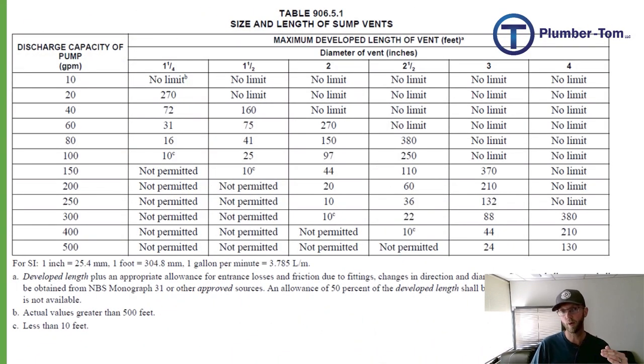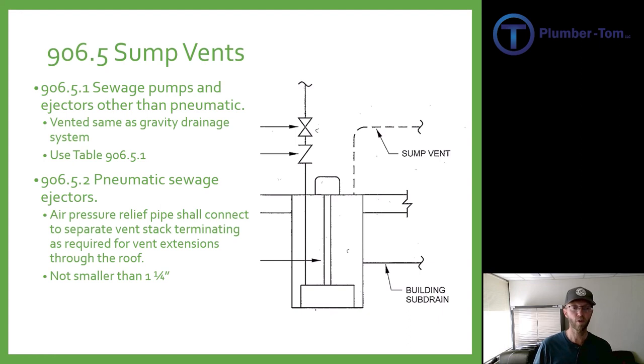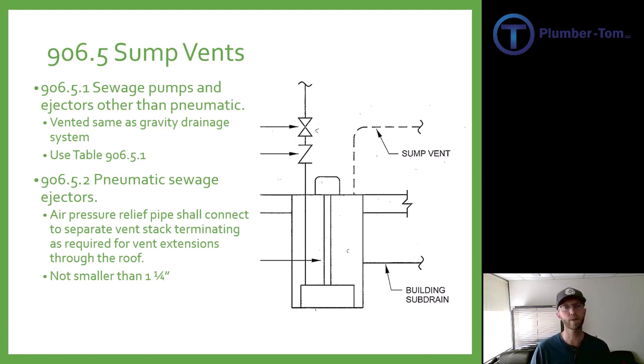Once we know our gallons per minute and our developed length, we come up to the top of the table to find our vent size. Section 906.5.2 covers pneumatic sewage ejectors and states that the air pressure relief pipe shall connect to a separate vent stack terminating as required for vent extensions through the roof. Most of the ones we deal with are electric, so that would not as much apply. Pneumatic ejectors also have a minimum pipe size of one and a quarter inch. Sumps just will not work if air is not able to replace the fluid being pumped out — they have to have vents. I made the mistake of failing to install one once, and trust me, it doesn't pump when there's no airflow.